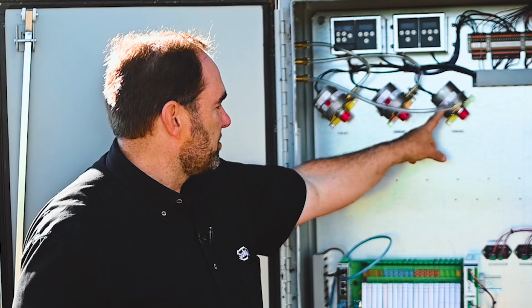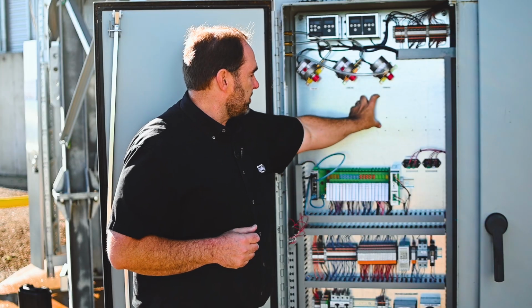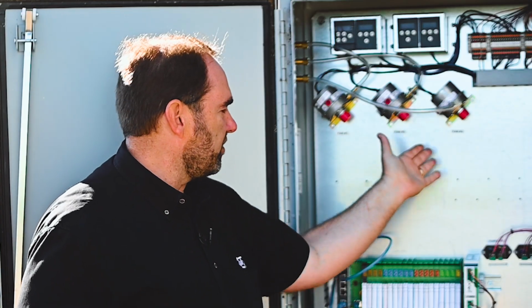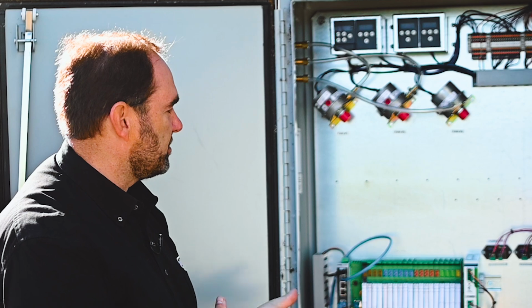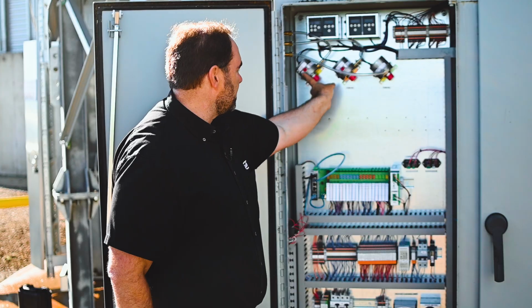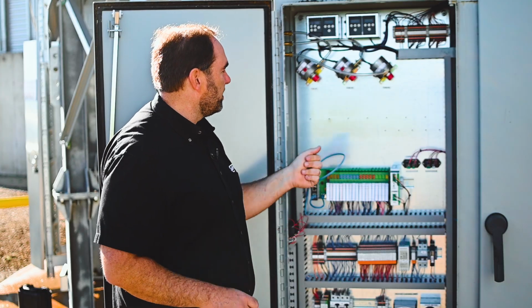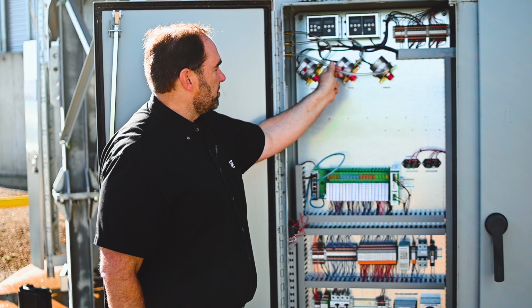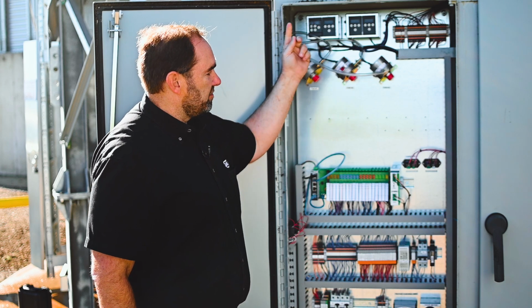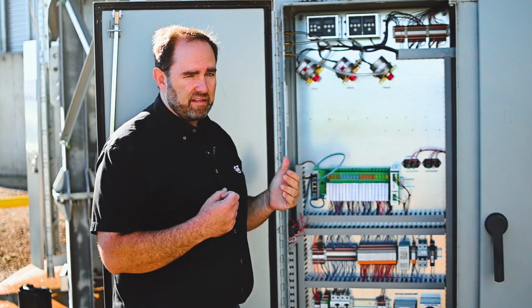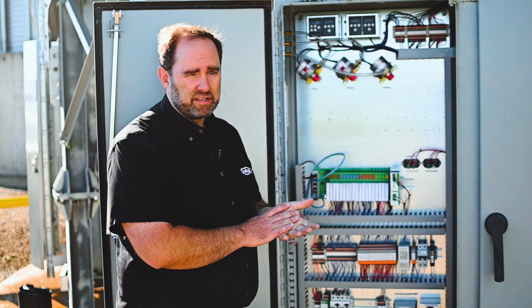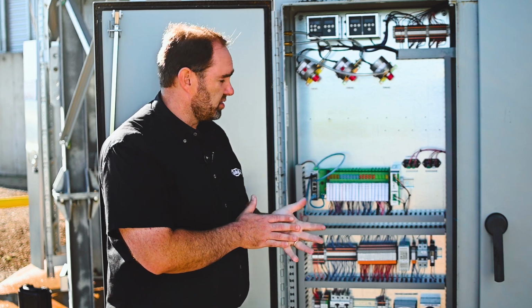Next, we've got 3 air switches, and newer models might actually have a TAN style air switch right below that and actually use 2 air switches per fan. But these basically verify that the fans are on. These lines are going to run, they're going to turn into a copper line and run to the inlet venturis of the fan, and they basically just sense vacuum. When they sense vacuum, it knows the fan is on, and it's then safe to start a heater.